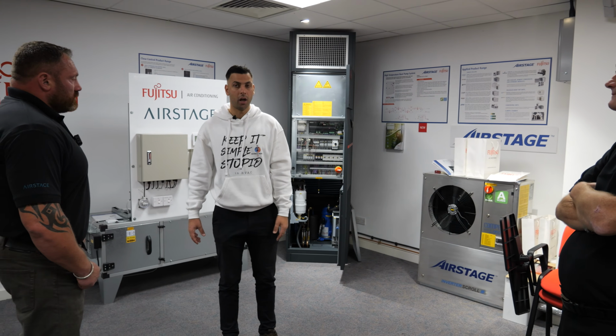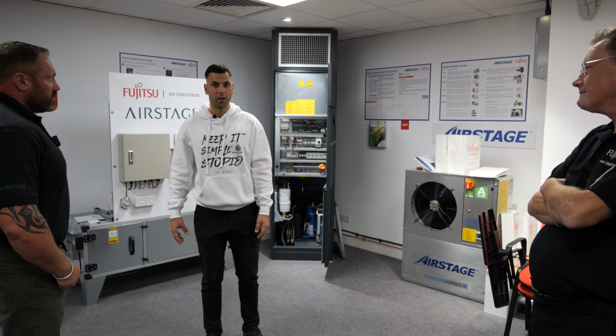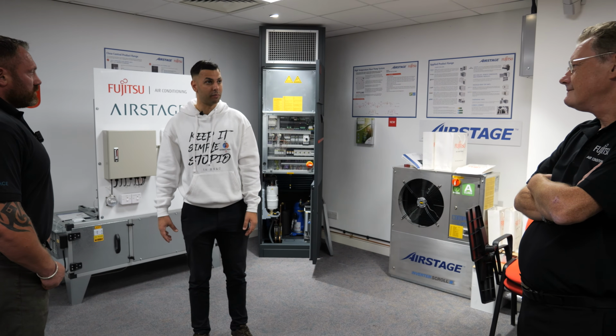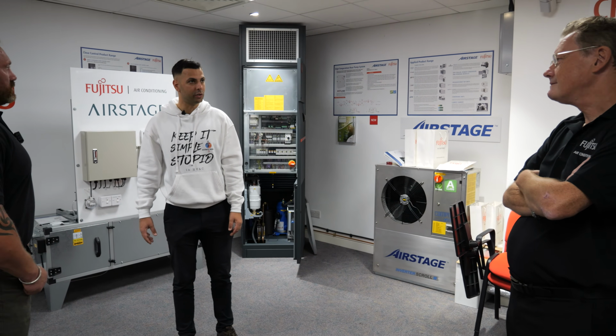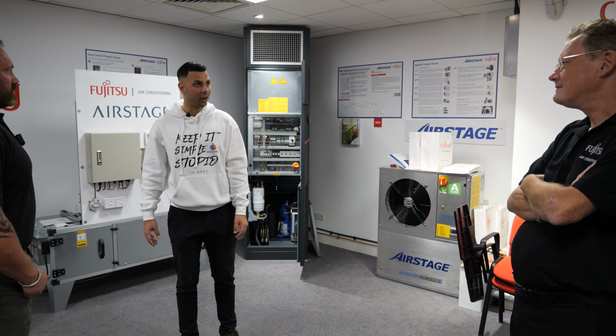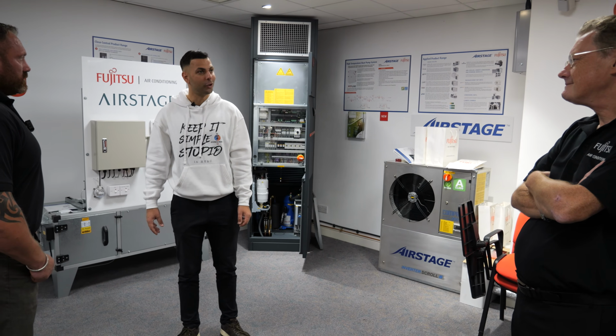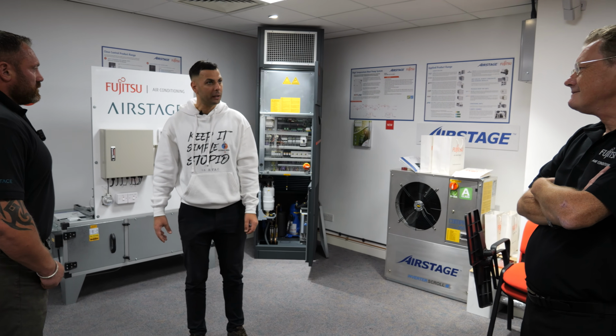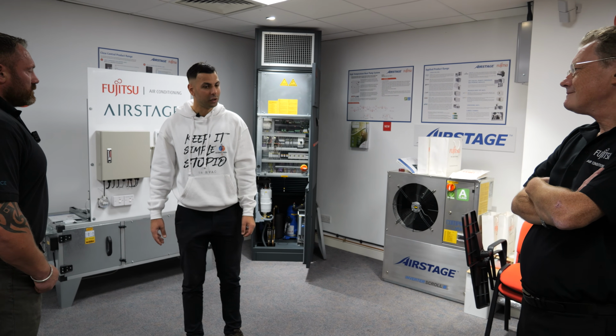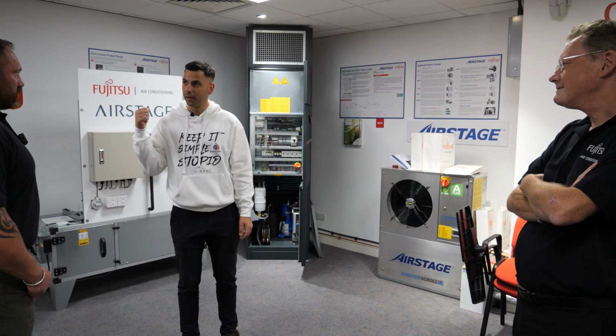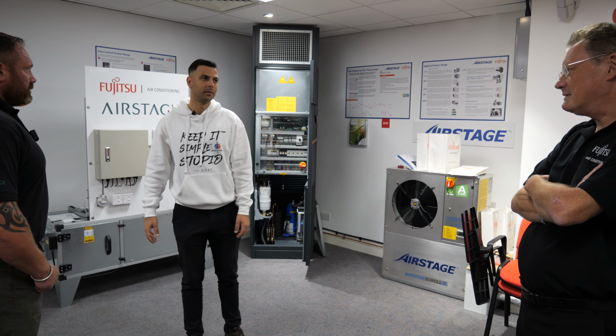Yeah. And I think I know two courts immediately where they've had brand new Systemair units with Daikin solutions, and they've had power issues on the site where the installer has bodged turning off three-phase supplies because they haven't got enough power to the building. Because they've had to use three-phase preheat. So this would eliminate that completely. Yep. Down to -7. Damn.